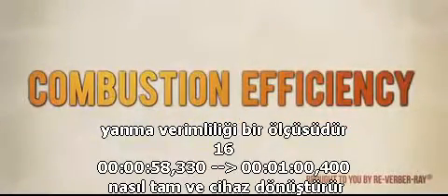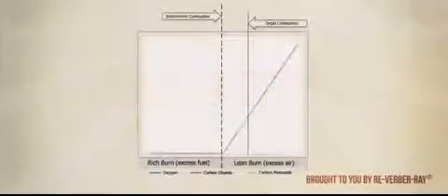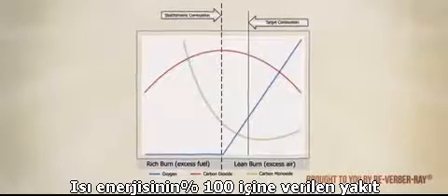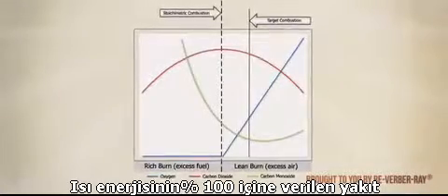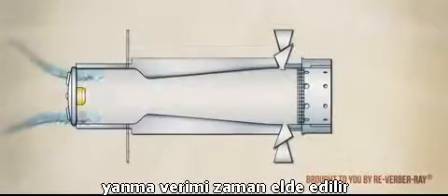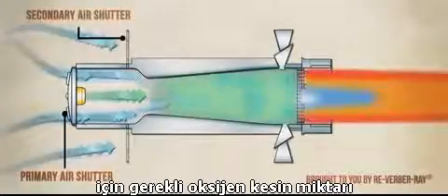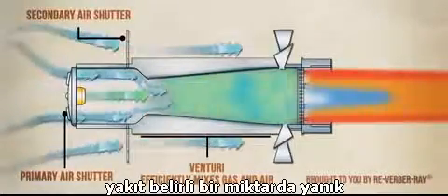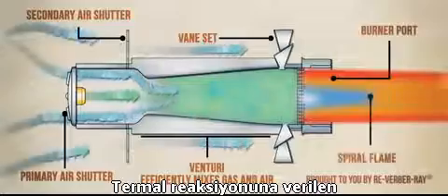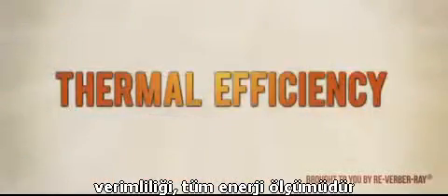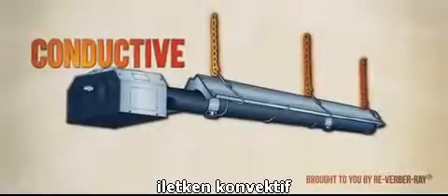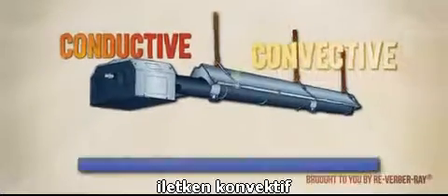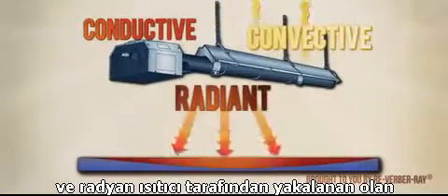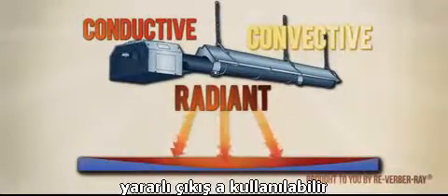Combustion efficiency is a measure of how completely an appliance converts the supplied fuel into heat energy. 100% combustion efficiency is achieved when the exact amount of oxygen required to burn a specific amount of fuel is supplied to the reaction. Thermal efficiency is the measure of all energy, conductive, convective, and radiant, captured by the heater, which is available for useful output.